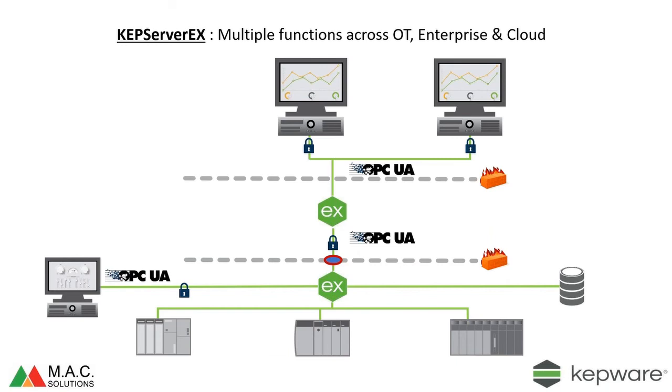And this is a very common solution we see. In fact, it's also possible to put 2 copies of KEPServer down on the OT and have the DMZ copy of KEPServer able to connect to either the duty or the standby, depending upon the status of those 2 redundant pair servers. So you can do lots of different useful topologies using this type of approach.